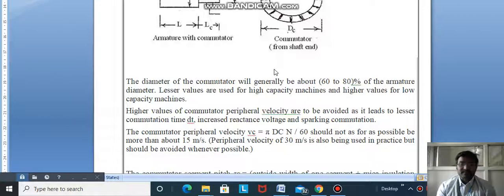The commutator peripheral velocity Vc = π Dc N/60 should not, as far as possible, be more than 15 meters per second. Peripheral velocity of 30 meters per second is also used in practice but should be avoided whenever possible.